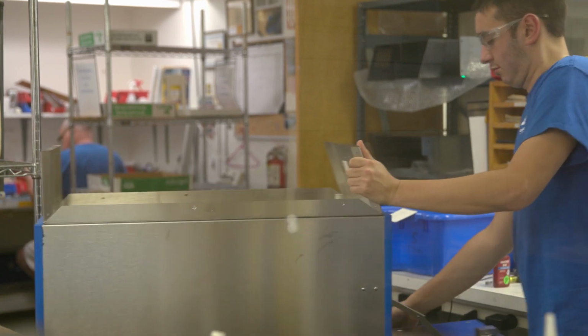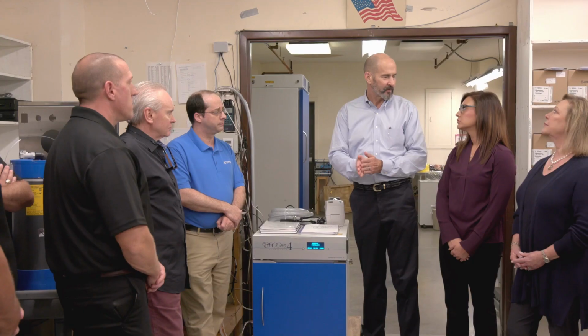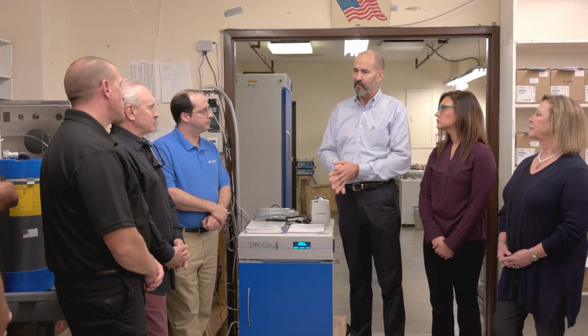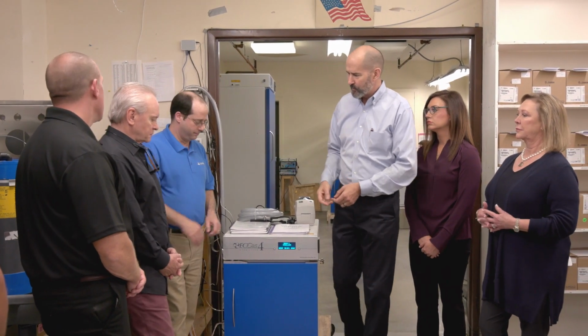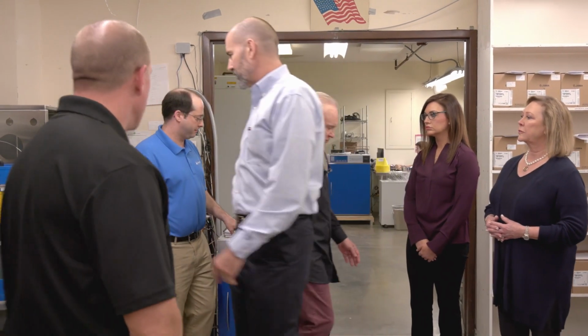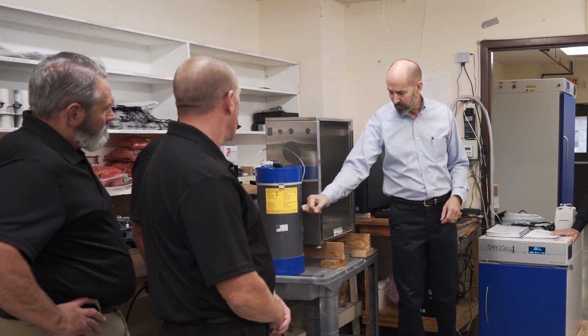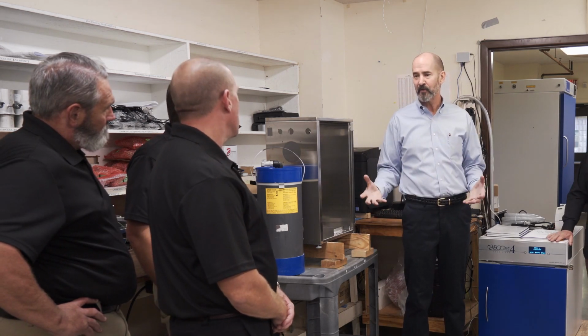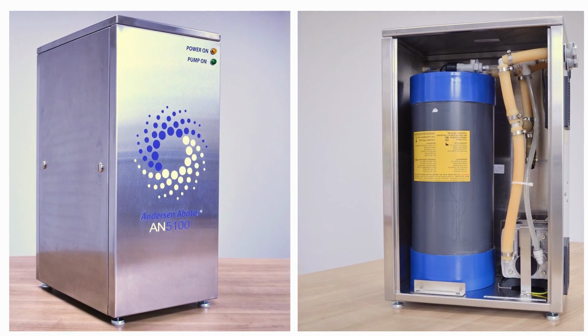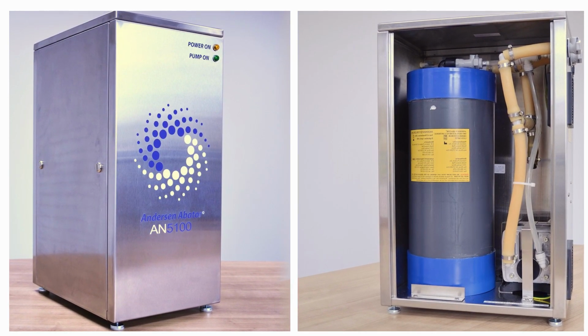Justin, we were talking previously about the environment and growing concerns about the release of chemicals into the environment. And Dr. Hunstead, behind you, we've got the shell and the heart of one of our scrubbers, which we refer to as an emissions abater. This runs on a very simple cartridge that chemically captures the ethylene oxide that's released from our systems. And we are calling this a zero emission process when you use one of our abaters. In truth, you're releasing about 0.17 grams of gas per cycle. So it's not zero, but it's pretty darn close.